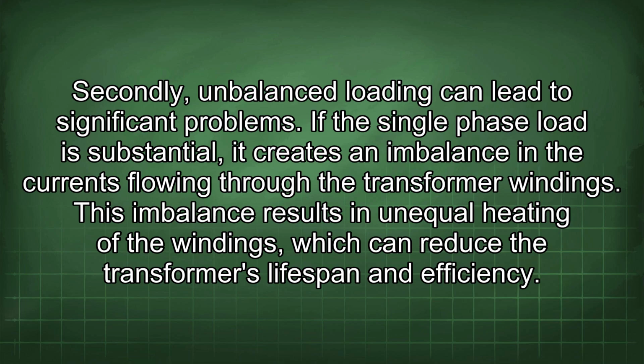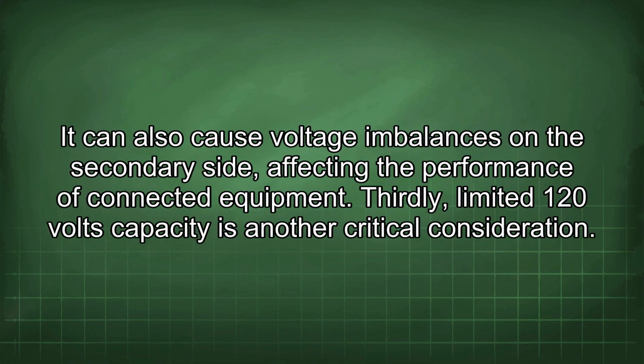Secondly, unbalanced loading can lead to significant problems. If the single-phase load is substantial, it creates an imbalance in the currents flowing through the transformer windings. This imbalance results in unequal heating of the windings, which can reduce the transformer's lifespan and efficiency. It can also cause voltage imbalances on the secondary side, affecting the performance of connected equipment.